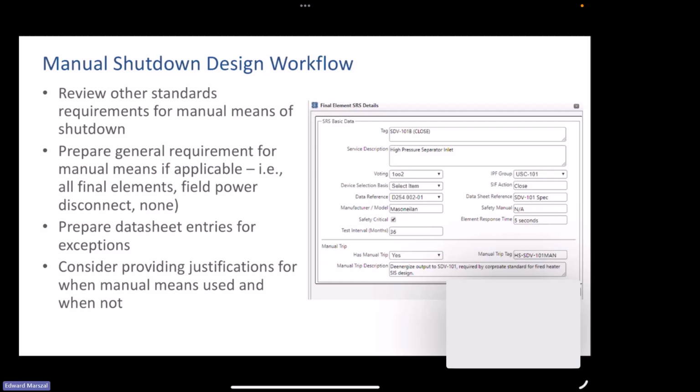If you have a pipeline, you're also going to need to follow, well, let me step back a little bit and say that in the United States, so I'm only going to speak to the rules in the United States, there are Department of Transportation DOT regulations that are going to tell you about the design requirements, including the spacing required for manual shutdown valves.